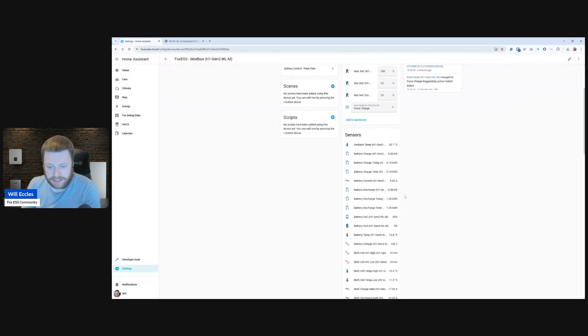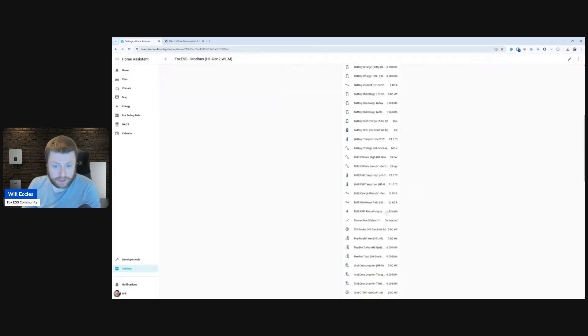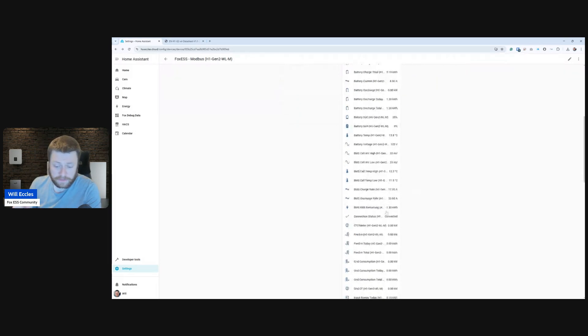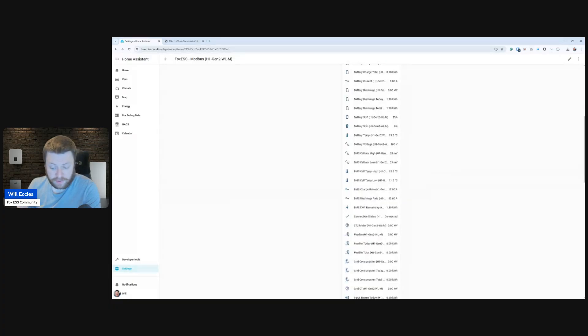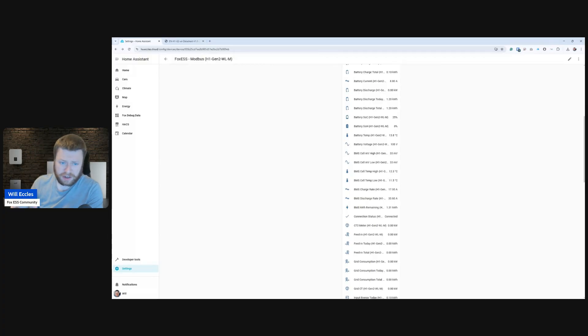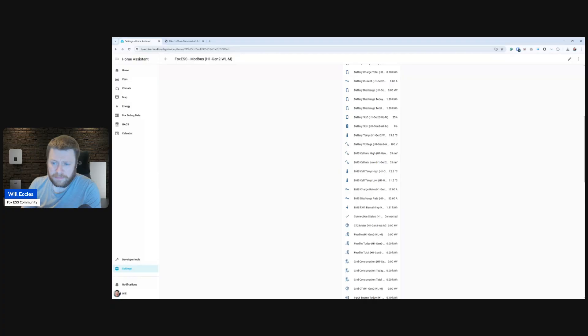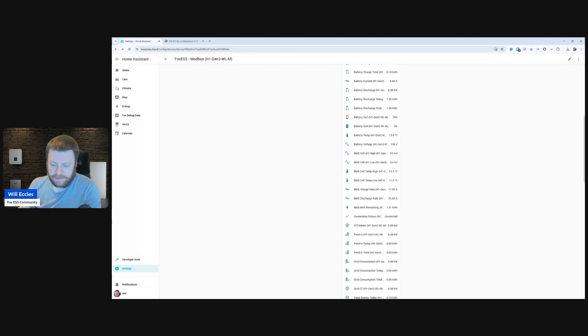In my tests, I've got all the same data that I would have if I was to install a RS-485 to Modbus adapter or Ethernet adapter, which is a very common approach. But when you add an external adapter, you've got to worry about cabling. You've got to cable into and connect two cables into the COM ports for the connection.